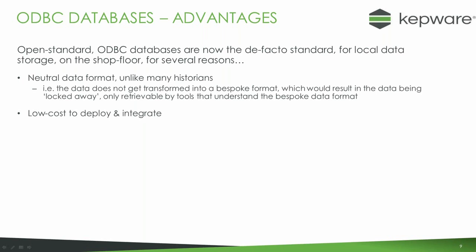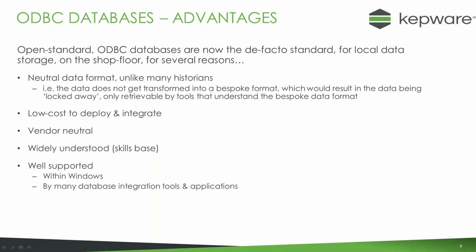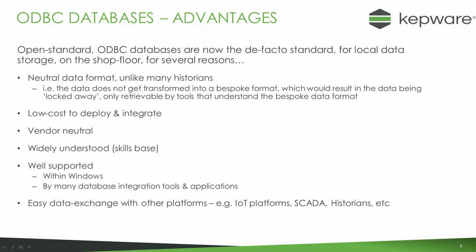Storing databases on the shop floor is seen as a good thing these days, and the data is not transformed into a bespoke format like some historians do, but is retrievable by many tools. It's also low cost to deploy and integrate a database — many of the tools are free. It's vendor neutral, so it's not owned by anyone; ODBC is a standard across multiple different suppliers. Because of that, there's a very wide skills base. It's well supported in Windows, with many database integration tools, reporting tools, and other applications to turn data into information and knowledge. And it's very easy to exchange data between databases and other platforms — IoT, SCADA, historian, or reporting platforms can all ingest data from a database without any issues.